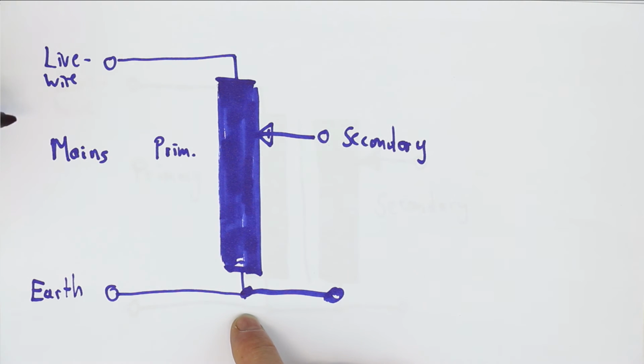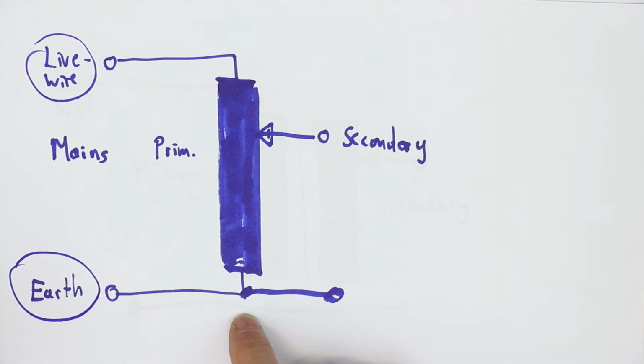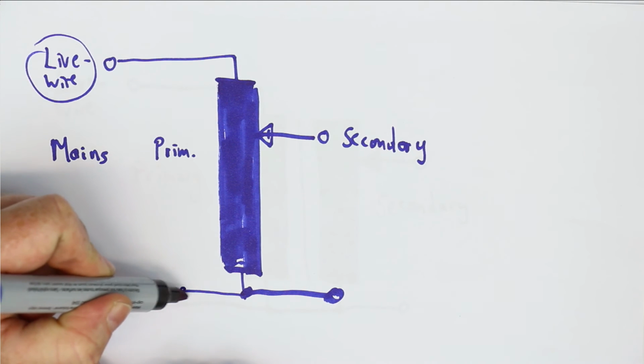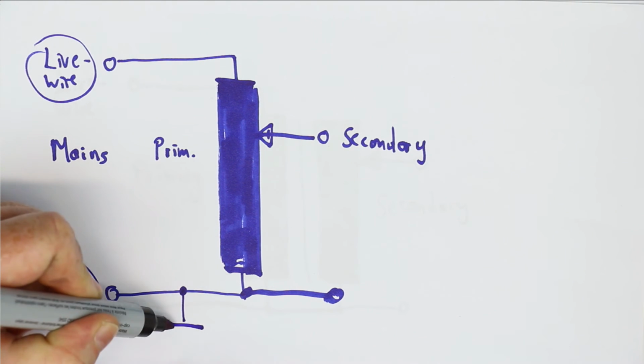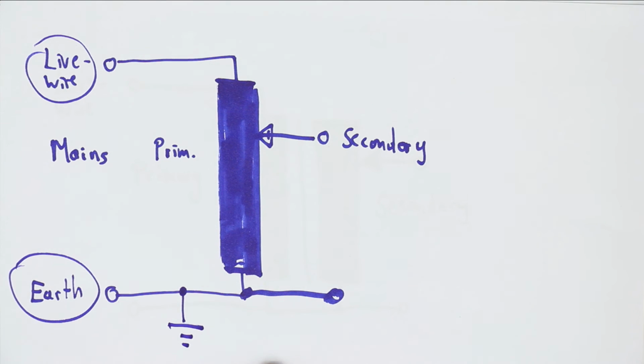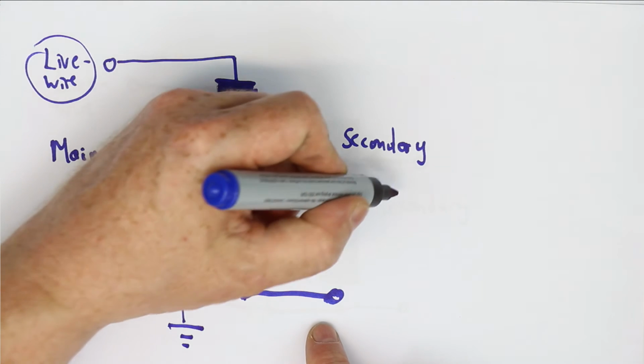And now it also becomes clear why it is mandatory to have the live wire of your mains voltage connected on the upper side, and the lower side must be connected to earth. Otherwise, imagine here the secondary goes to your device under test.